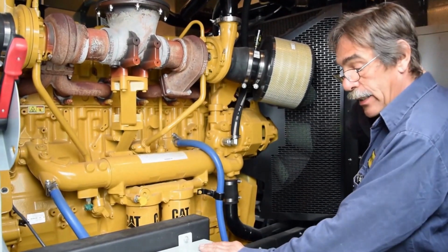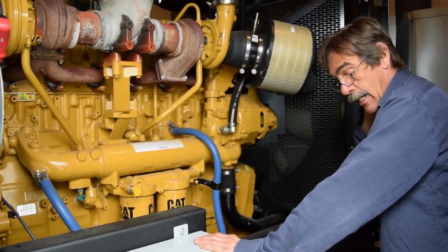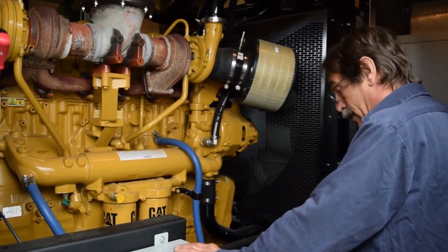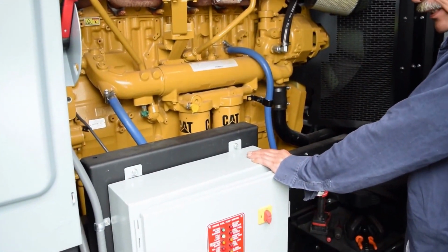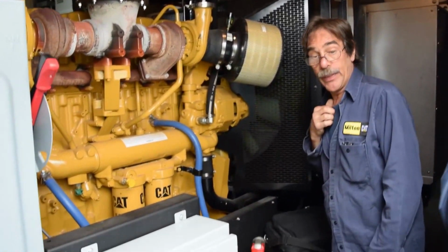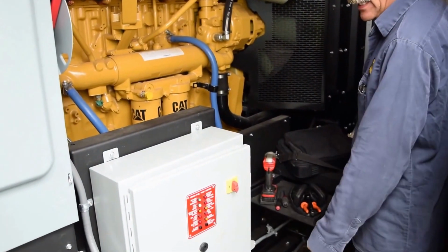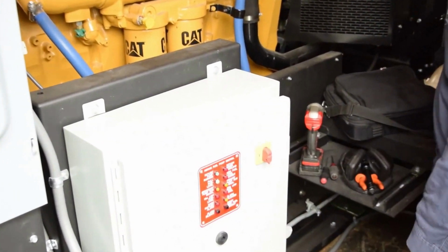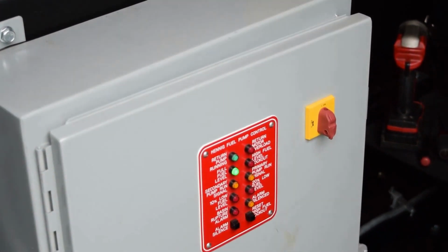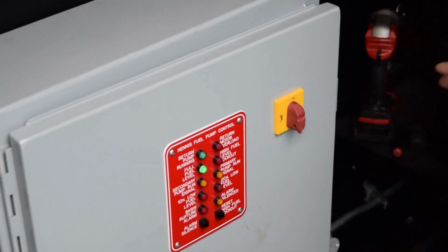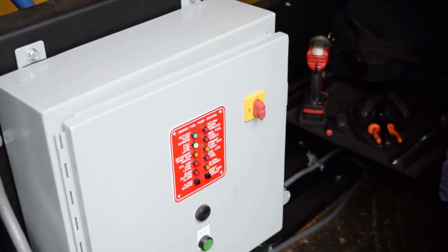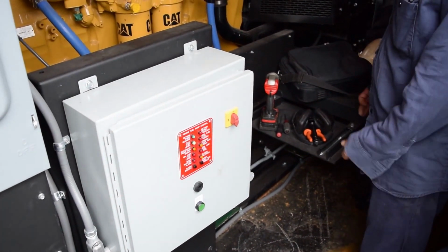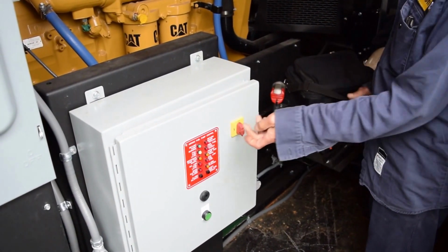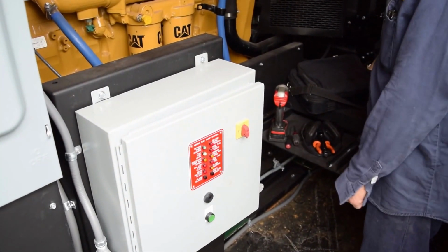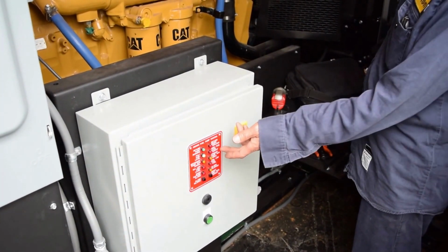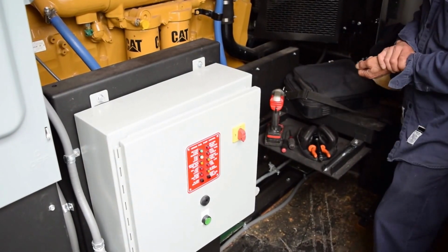We also have our day tank controls. That's what we were testing today. There's a main tank downstairs and a day tank upstairs. We have low fuel and high fuel alarms. We actually have two low fuel alarms. The tank pumps down, and we turn on our primary pump, and that pumps the tank back up. If that pump happens to have a failure or something, it'll pump down some more, and the second pump will turn on and pump us up to the full level. If we overfill, the return pump will activate, and above that level, we'll get a return lockout.